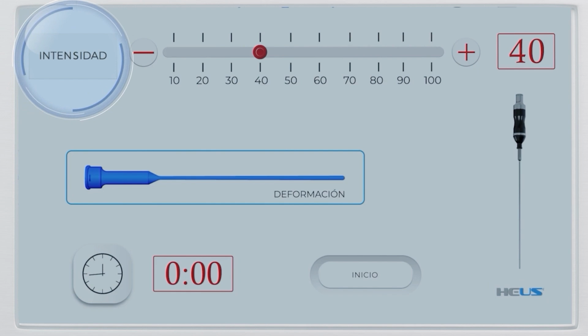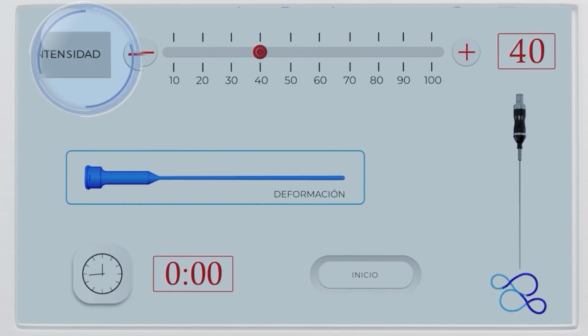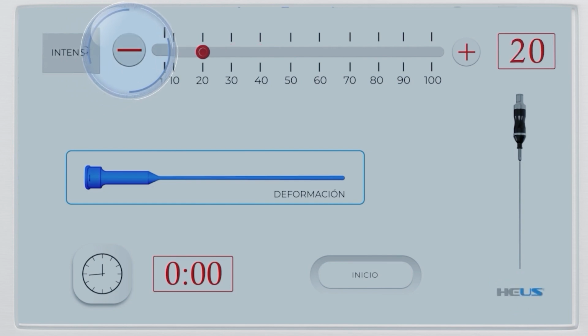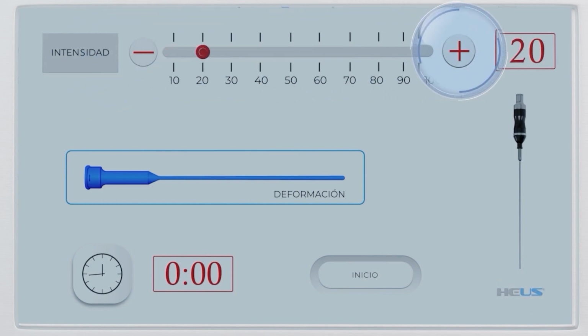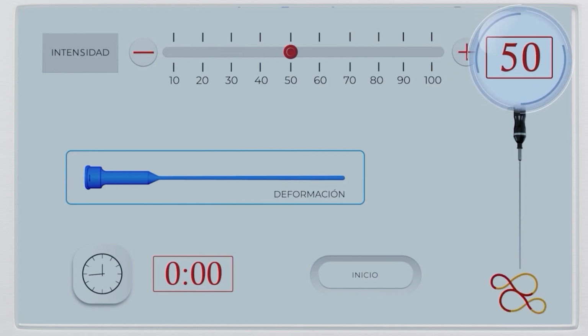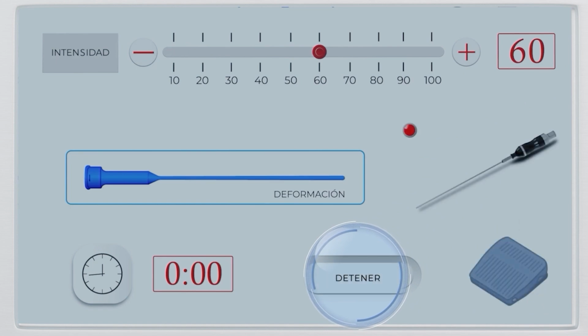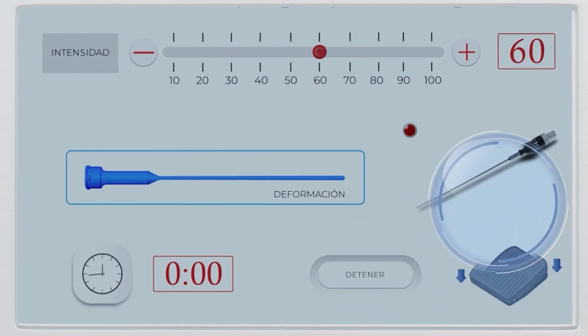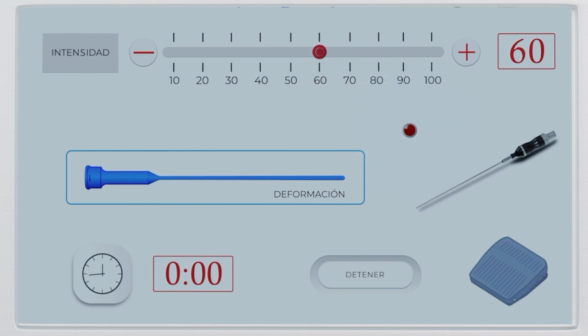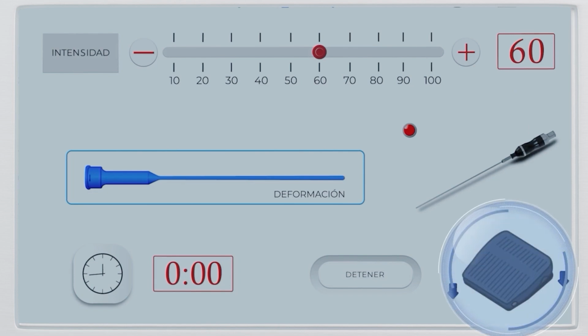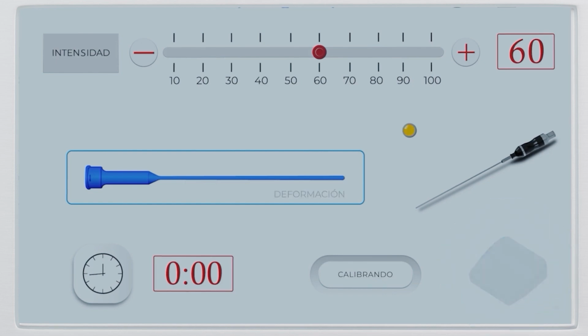Intensity allows you to adjust the power of the ultrasound for emulsification. Select the minus sign to decrease intensity or the plus sign to increase it. The red box will display the percentage of the selected power. Start. Pressing this button will put the device in working mode, and the screen interface will change to show us some new active icons. At the bottom, an animation of the pedal will be displayed, indicating that only the device will emulsify or homogenize when pressed with the foot.